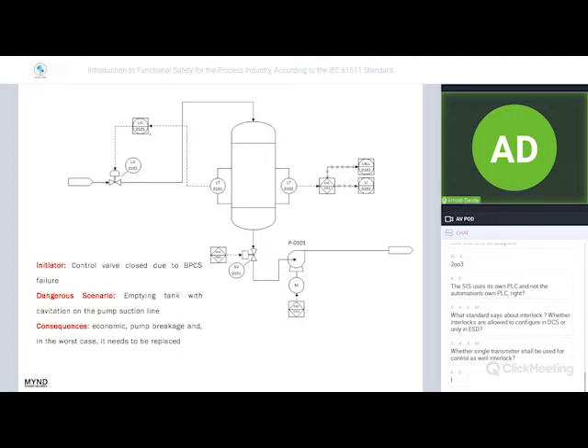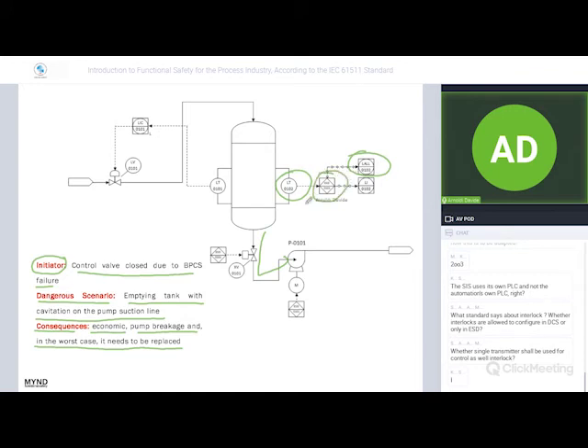So in this case, during the HAZOP, we identify the initiator, that is the control valve closed due to BPCS failure. The dangerous scenario is the empty tank with cavitation on the pump suction line. And the consequence, we have only an economic consequence: pump breakage, and in the worst case, it needs to be replaced. We identify a single function. The function will be a level transmitter, and with low level, through the safety PLC, stop the pump. This is the correct safety instrumented function in order to protect the pump from cavitation.